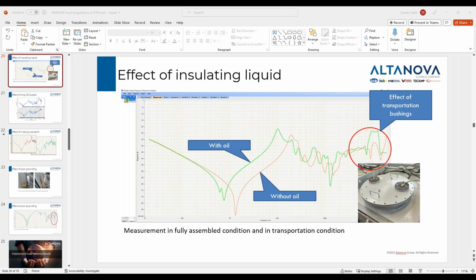Which transformer can't be measured with the SFRA method? I'm meaning a transformer for some special usage like starting a gas turbine. Well, any transformer will be measurable. If there is a winding inside, you will be able to measure it. The main thing is that the less complicated the windings, the less complicated the trace is. So if you have a small transformer with a low voltage winding operating, let's say at 600 volts, and this is foil winding, just a few turns, your response will be more and more flat, and it will not show you too many details. So the less complicated the winding, the fewer details you can see, and you will see less from the test.